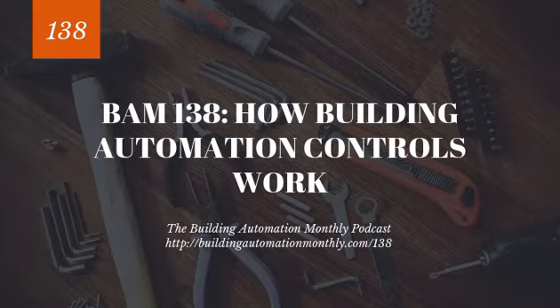And this is a huge area that a lot of specifications and building automation standards miss. They don't define the expectations of the graphics. They don't define the expectations of the user. They don't list out who's going to be using the system, how they're going to be using it. They don't restrict access to graphics based on user. I mean, that's a whole episode in itself. Graphics strategy, user strategy, categorization versus roles, etc., etc.